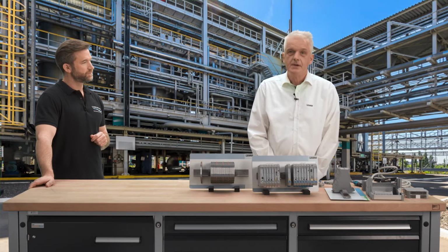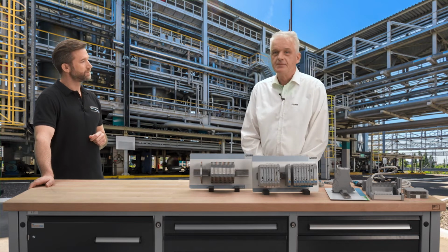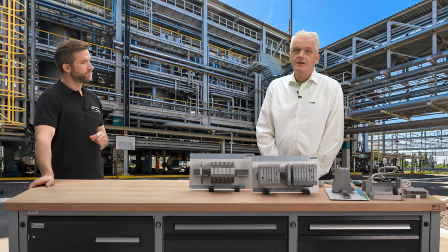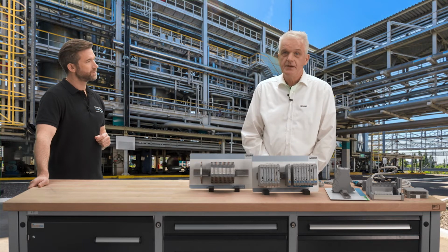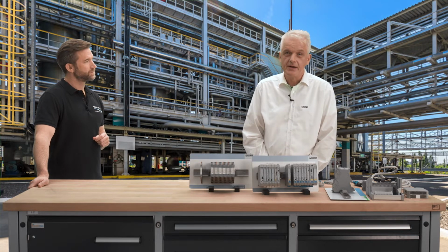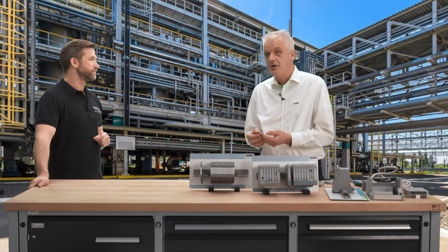For low power operations like measurement and control technology, the method of ignition protection type intrinsic safety, Ex i, is definitely worldwide the dominant one. And this is due to the following advantages. Cost effective due to no expensive solid housing constructions like Ex d, flame-proofed enclosures. One of the few types of protection which is permitted in Zone 0, and hot work permits are not required, so field instruments can be calibrated or maintained while power is on.